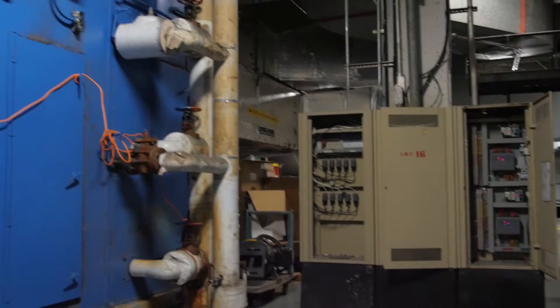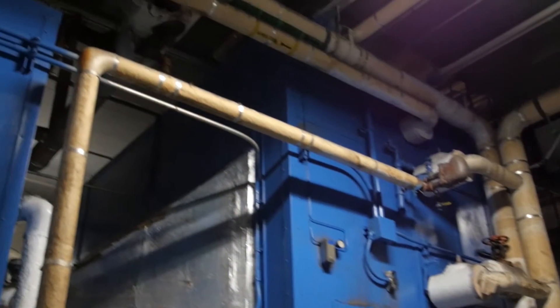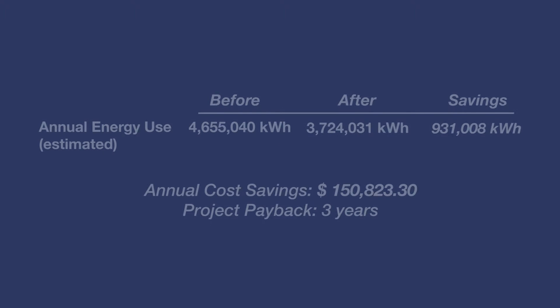The project started September 2015 and was completed December 2015. We are currently in the process of setting up communication from the control to the BMS panel. The total cost for this project was $500,000. The total savings is 931,000 kilowatt hours per year, the annual cost savings is $150,000, and the payback period for this project is three years.